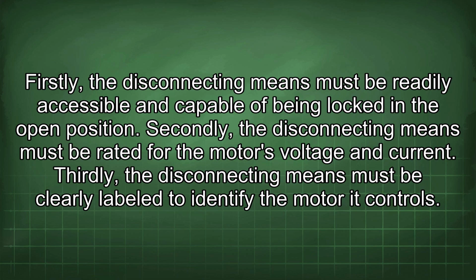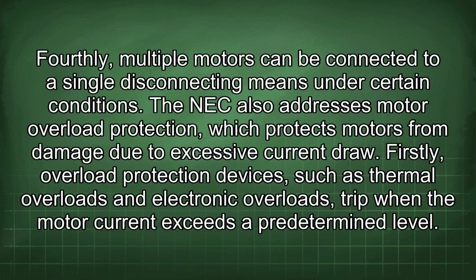Secondly, the disconnecting means must be rated for the motor's voltage and current. Thirdly, the disconnecting means must be clearly labeled to identify the motor it controls. Fourthly, multiple motors can be connected to a single disconnecting means under certain conditions. The NEC also addresses motor overload protection, which protects motors from damage due to excessive current draw.